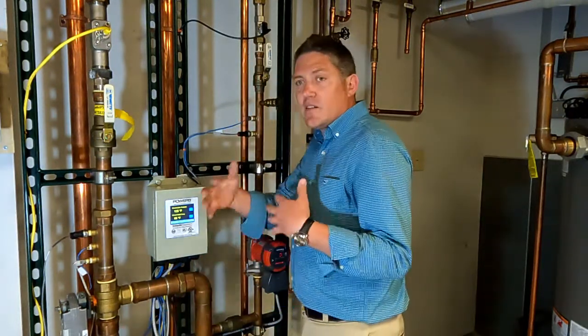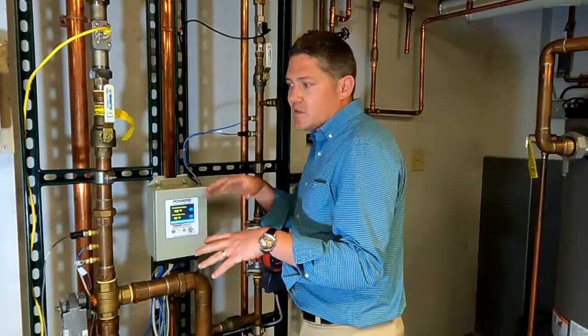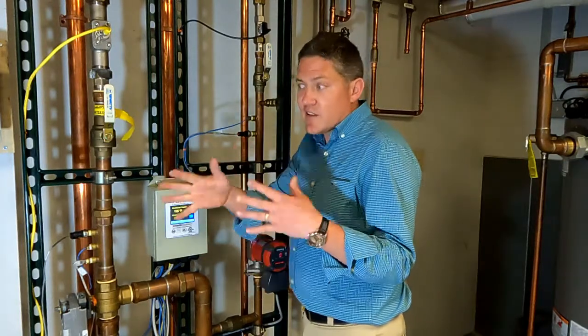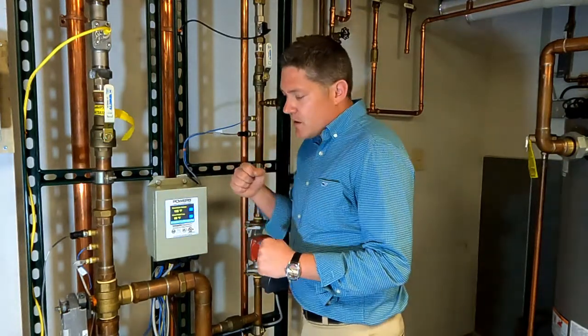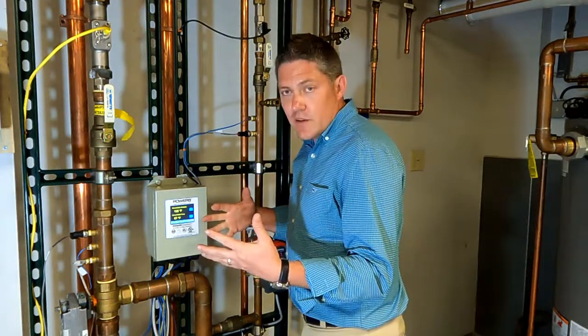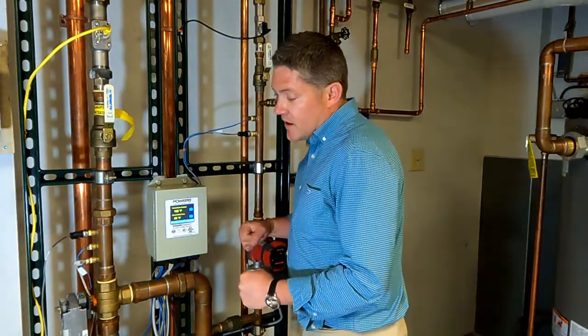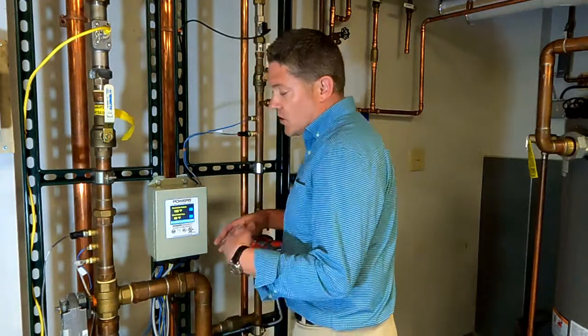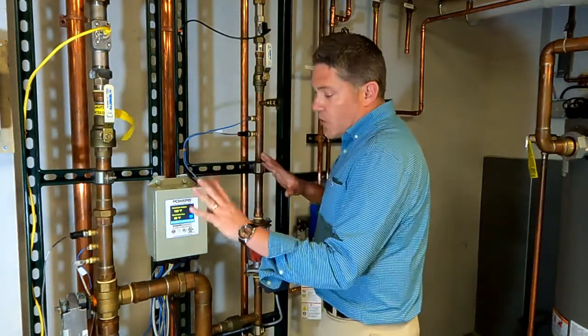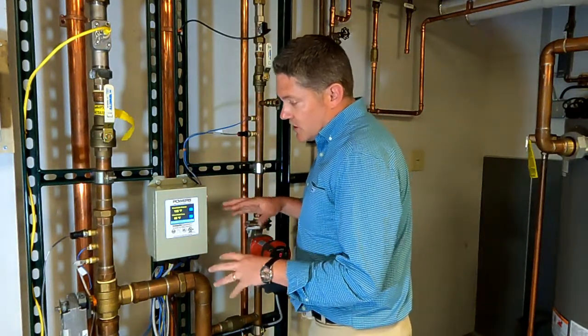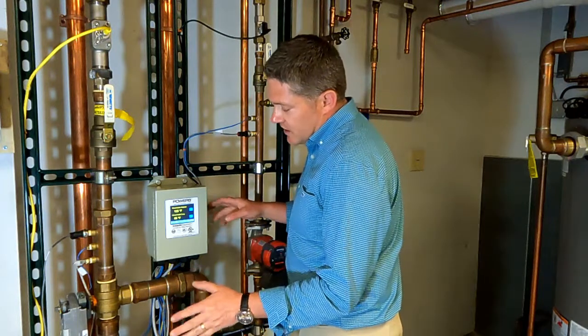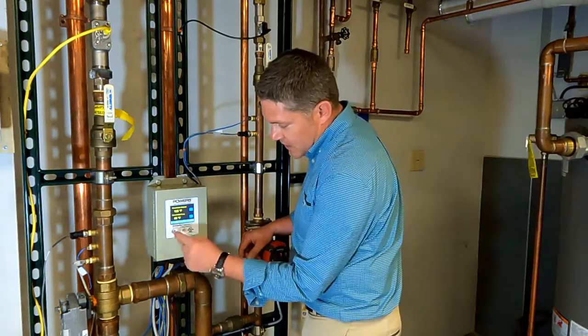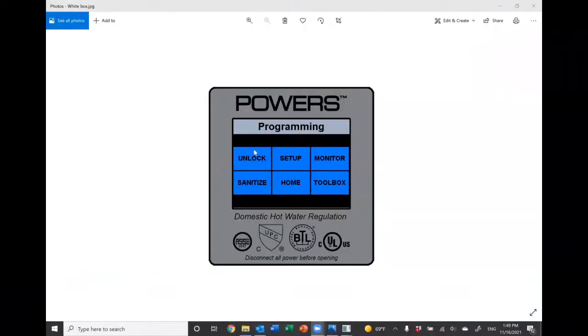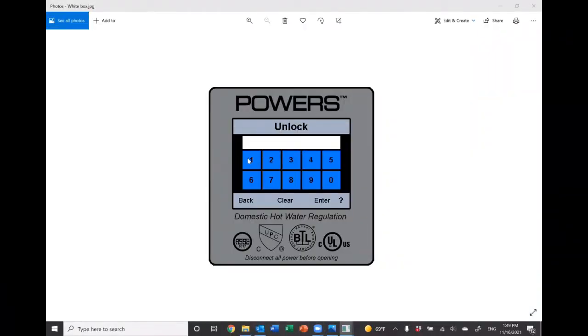So it can help to troubleshoot and diagnose problems in that way. It looks like in this case, your hot water heater is undersized, or it's not enough capacity and it ran out. So those data points can be very beneficial on a job site. As far as setting this thing up, you hit the program button, right? And it's password protected. There's a default password that you can plug in, or this can be changed by the facility to whatever they want.